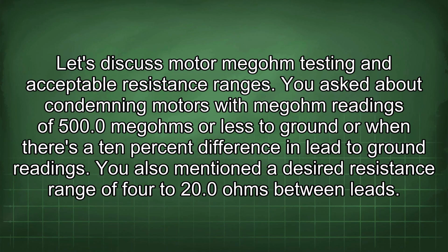Let's discuss motor megohm testing and acceptable resistance ranges. You asked about condemning motors with megohm readings of 500.0 megohms or less to ground, or when there's a 10% difference in lead to ground readings. You also mentioned a desired resistance range of 4 to 20.0 ohms between leads.